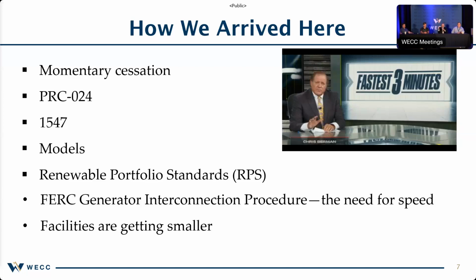So the other thing that we learned is that they really took PRC 24 as a requirement, or in other words, outside the curve, they interpreted that as must trip, not may trip. And that presented problems. IEEE 1547, for those familiar with that, those are distribution standards for connecting facilities on the distribution system. We discovered that they were bringing 1547 type philosophy to the transmission system. And of course, that doesn't work real well, right? Because there's very different needs on the distribution system as opposed to the transmission system.